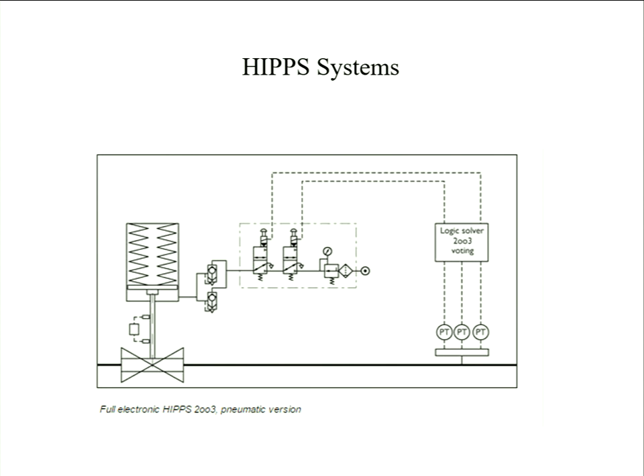Is there anything they can do to damage our system? And if the LNG terminals have, say, class 900 pipework, so they might have 140 bar lurking around within their terminal. The national transmission system isn't designed to that, so there has to be something that ultimately will protect us against a failure on their side, and it's the sort of HIPPS. So HIPPS is high integrity pressure protection system. So we'll move on to a quick gallop through sensors and transducers.